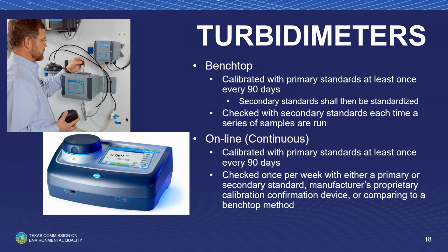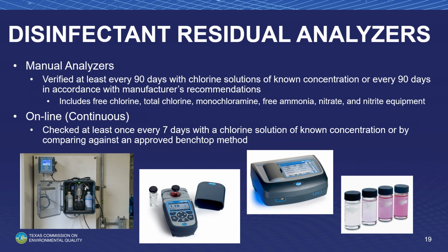So once again, like with your benchtop pH meter, here turbidimeters can also be very finicky. Each time you run samples through that turbidimeter, verify it with 1 or 2 of your secondary standards to make sure that it's still reading within a good range. Online continuous, those also need to be calibrated with primary standard once every 90 days. And then you need to check it once per week with either a primary or secondary standard or compared against a calibrated benchtop method.